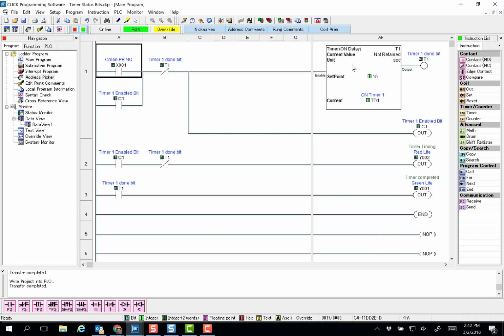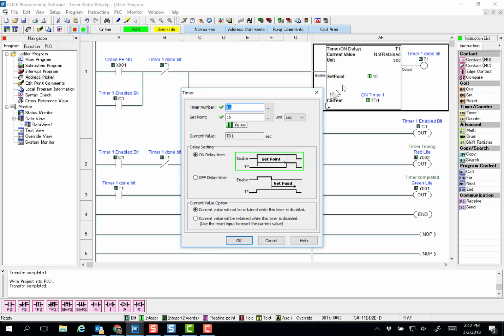But we've paralleled down, just Ctrl down arrow, and added a C1 bit, a timer. Could have been any internal coil, but I chose C1. And so whenever the timer starts, C1 will turn on. Then C1 will seal itself and allow it to run. This will run until timer 1 gets done, because the timer operates that way: when we enable it and then we disable it, it drops the time.